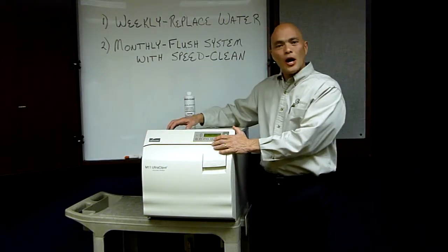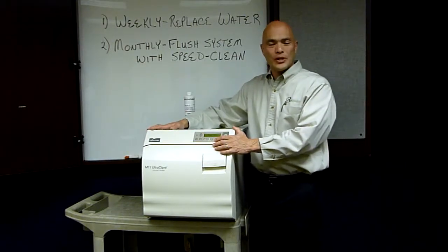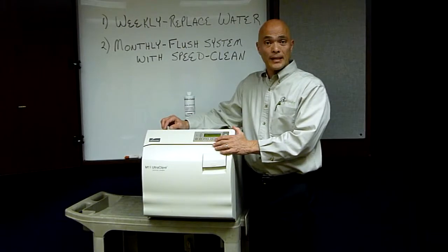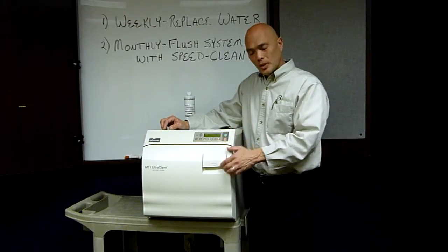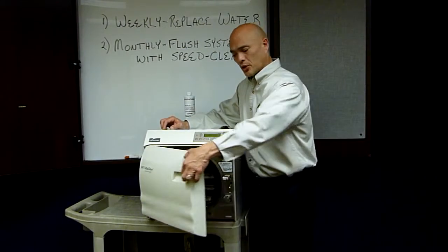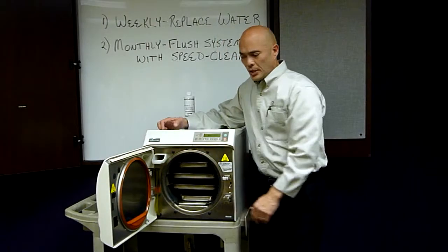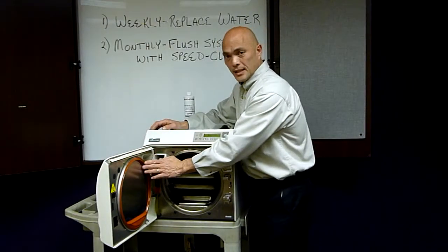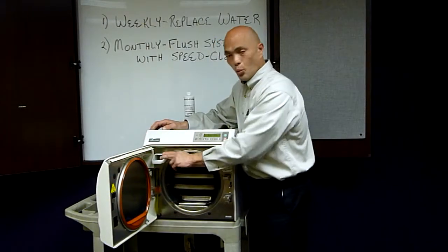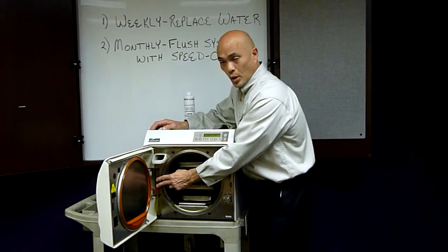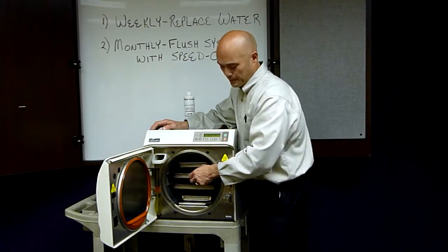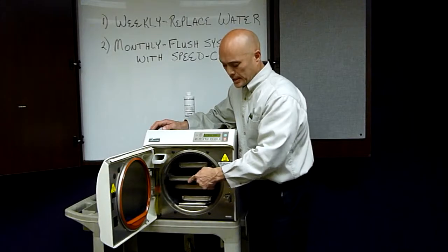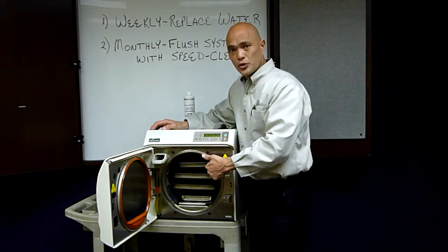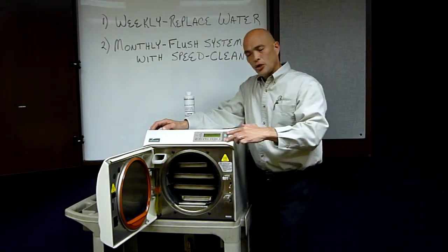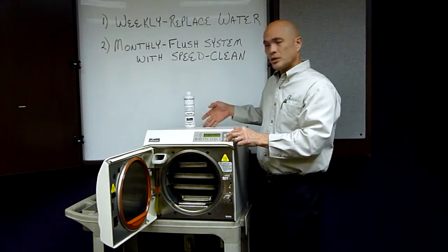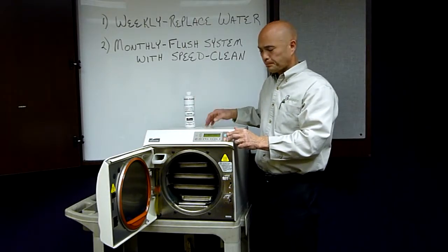Hi, I'm here to go over the operation and maintenance of your M11 sterilizer. I'd like to start off with the mechanics of it. To open the door, lift straight up on the handle, swing the door open. On the inside you have your door gasket, your door dam, your water reservoir fill, your water reservoir drain tube, your trays, your rack assembly which holds your trays in place, your control panel, and your safety relief valve.